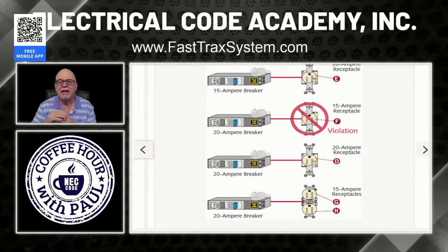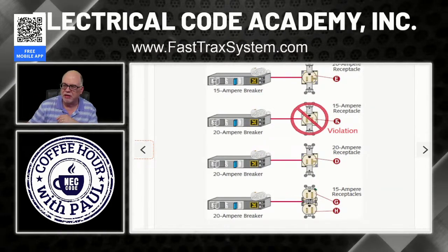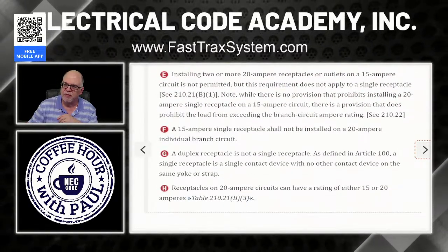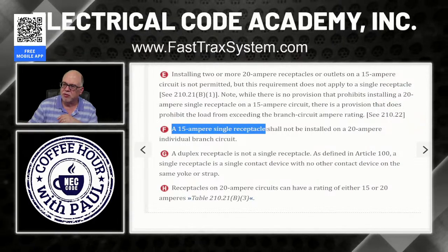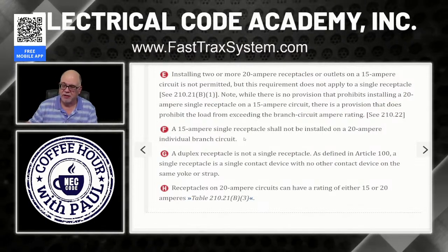That's what it says. And that is the part that I think people struggle with when they're determining what you can and can't do for the ratings of the receptacles versus the overcurrent protection. Okay, so that would be a violation. And if we go look at F, you'll see right here, it says a 15 ampere single receptacle shall not be installed on a 20 amp individual branch circuit. Why? Because as it says in 210.21, the single receptacle has to be what? Equal to or greater than the branch circuit rating. And it is not in this case.